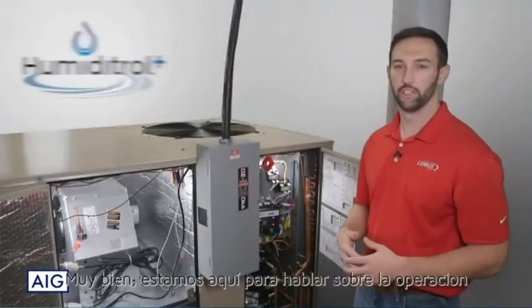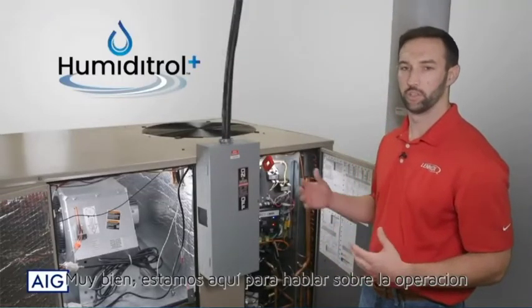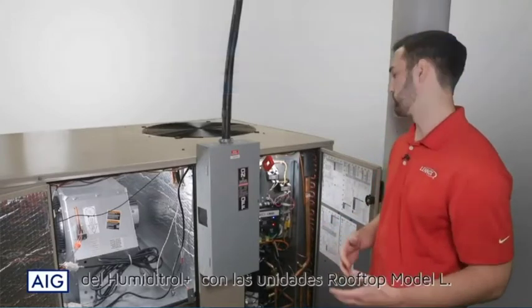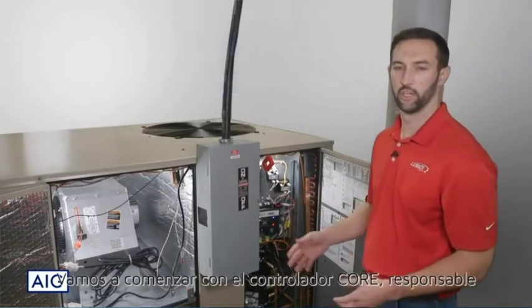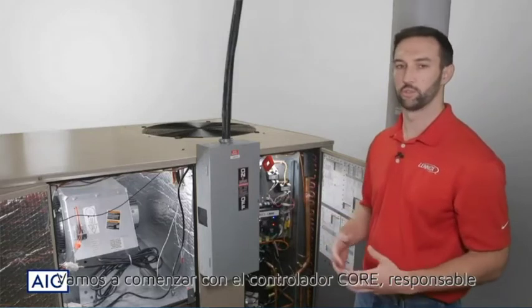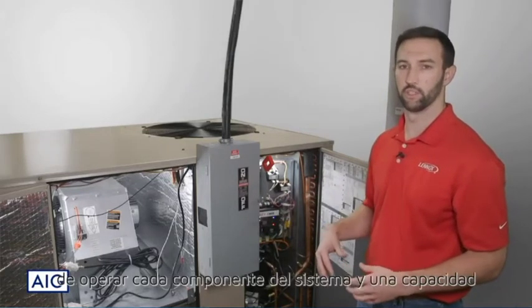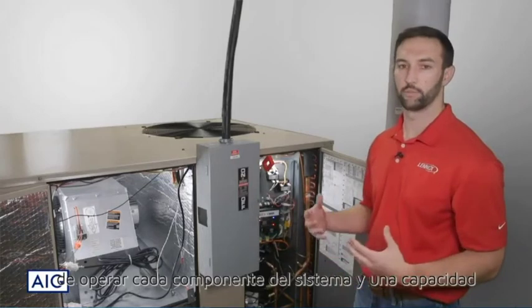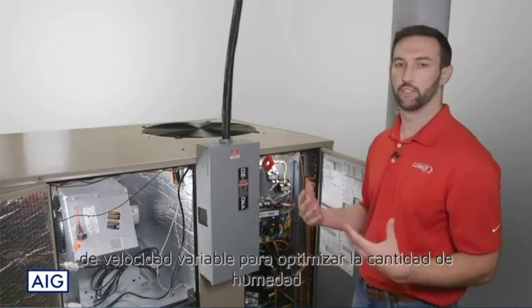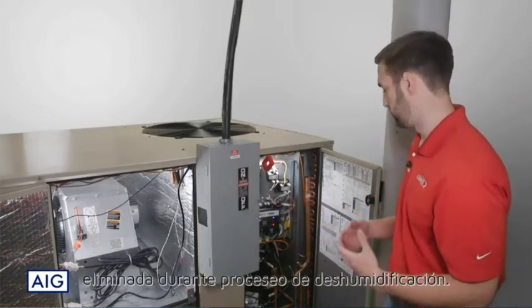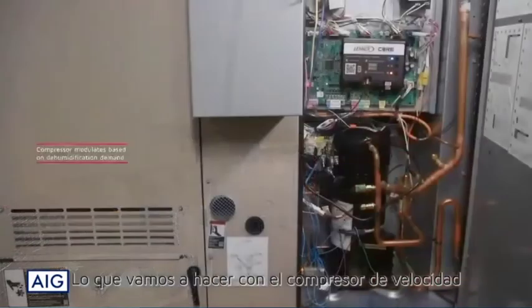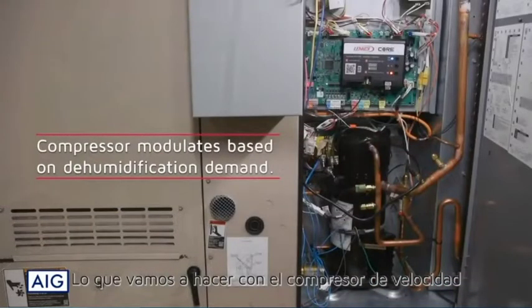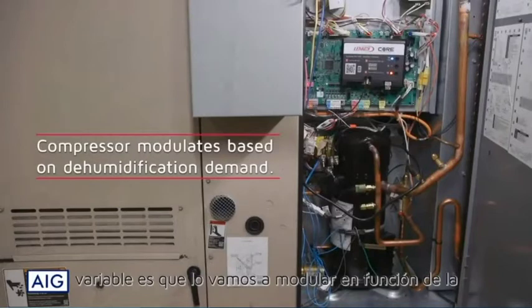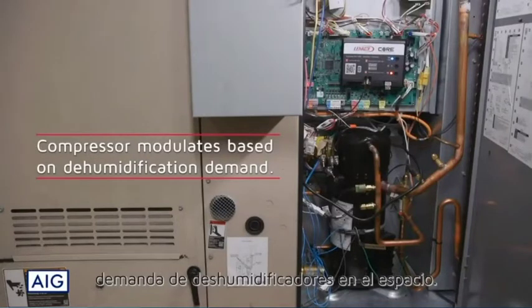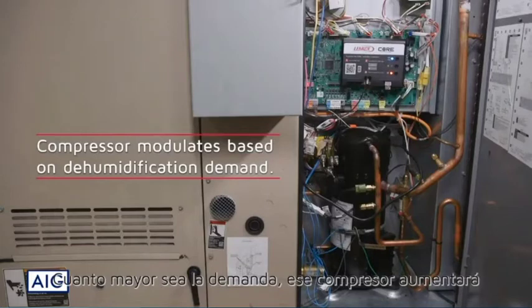All right, so we're here to talk about the Humiditrol Plus operation with the Model L rooftop units. Where we're going to start is the Lennox Core Unit Controller. The Core Unit Controller is responsible for operating each component of the system in a variable speed capacity to optimize the amount of moisture removed during a dehumidification call. With the variable speed compressor, we're going to be modulating it based on the dehumidification demand in the space. The higher that demand is, the more that compressor will ramp up and deliver more dehumidification capability.